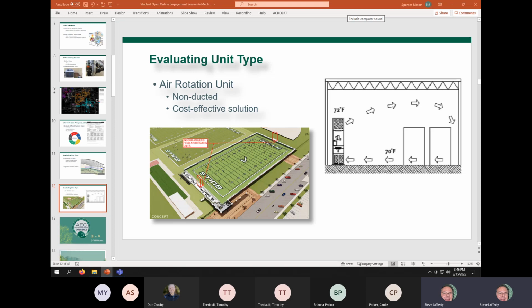Their main purpose, within a large volume of space, is to push air and rotate it continually, getting enough turnover so you have uniform temperature without any temperature gradients. One challenge is that without ductwork, you can't have interior partitions that would block airflow from moving between spaces. But since this was one open space, that wasn't a challenge for us.